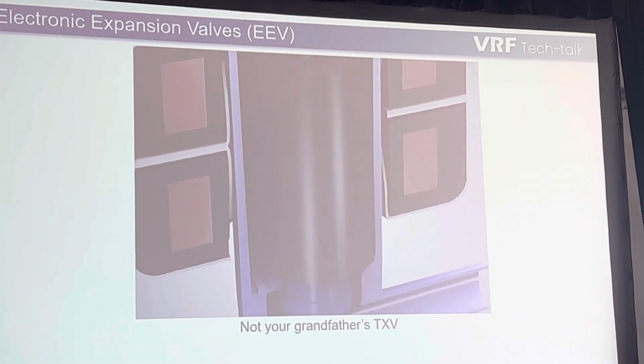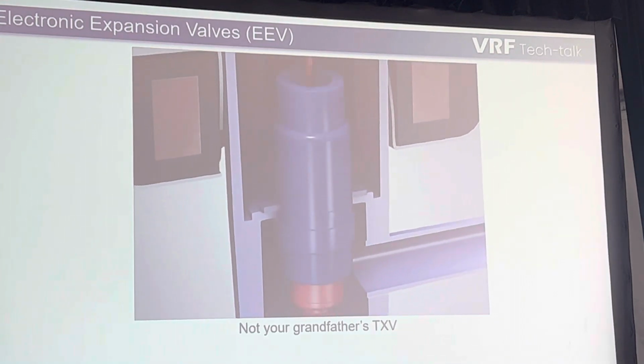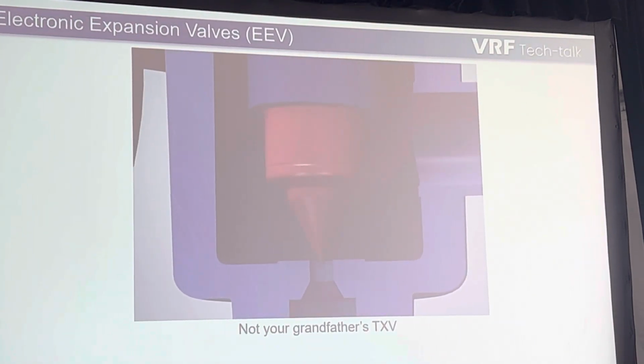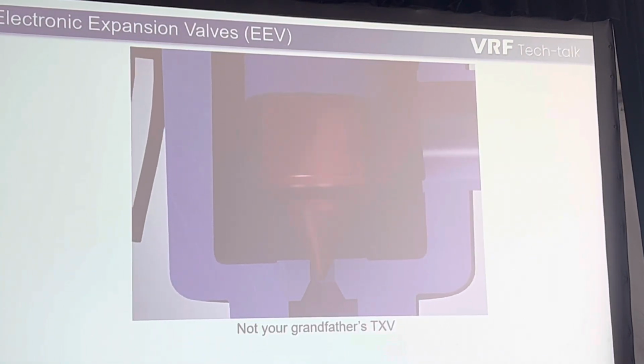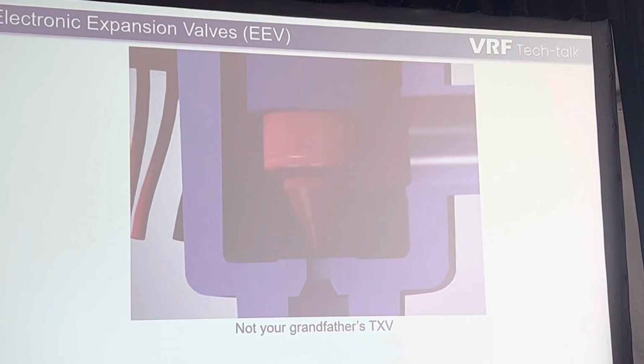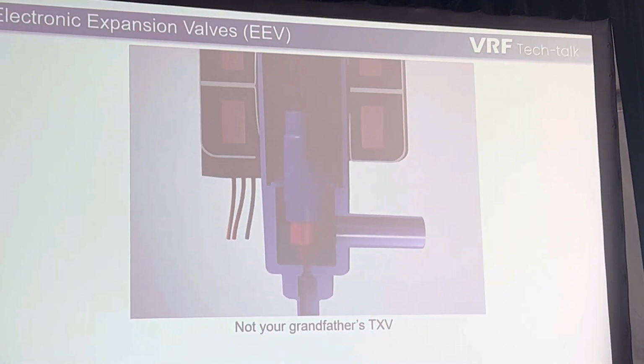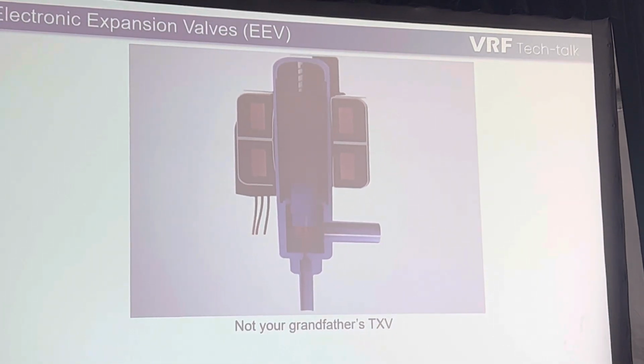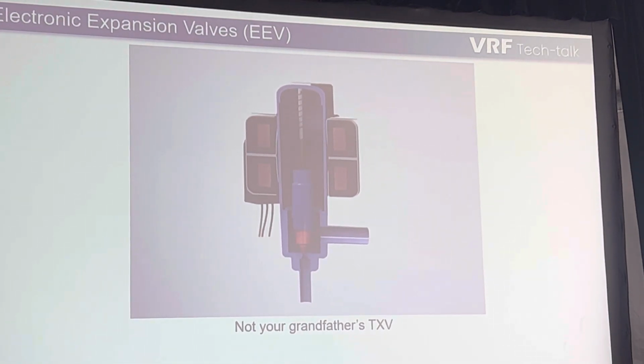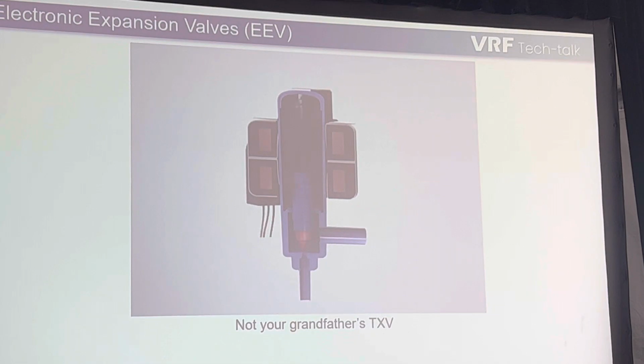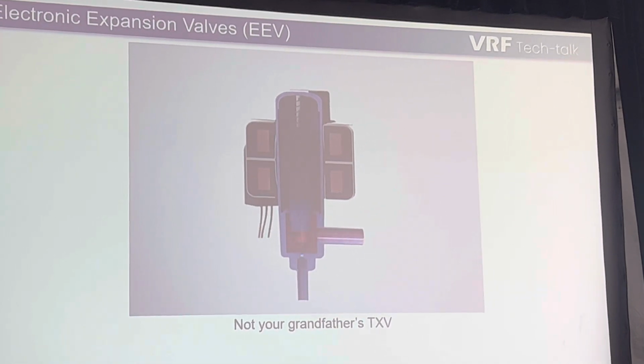That's essentially what it's doing. It's spinning away on the inside based upon the drivers on the indoor PCB, on the outdoor PCB, whatever's trying to control it. And as you can see, the inside spins as well, and this is how we meter our refrigerant flow. We'll add animation to that and show you exactly which way the refrigerant flows. There are manual magnetic donuts that you can purchase from your specific manufacturer to manually drive these.